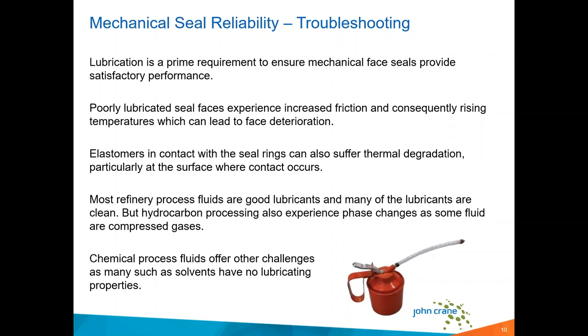So we can certainly take measures in the design of the seal to ensure we have adequate lubrication while minimizing leakage. We look at different materials. We look at different face technologies or treatments to help promote lubrication and minimize wear and heat. But then it all gets back to the transients, the upsets, the variables that may push those seal faces outside of a boundary where acceptable limits are going to be maintained. So we look at all the operating conditions and the environment of the seal, and how that in turn impacts the lubrication conditions for those seal faces.